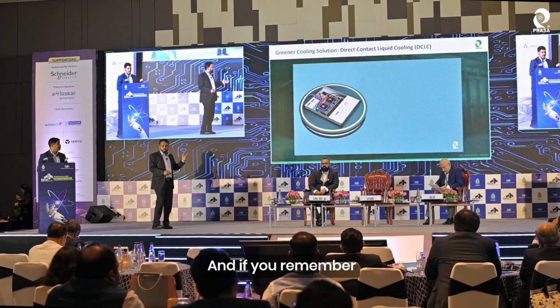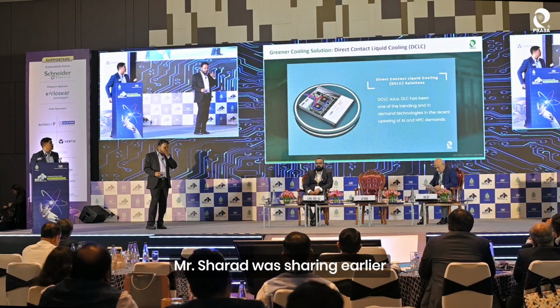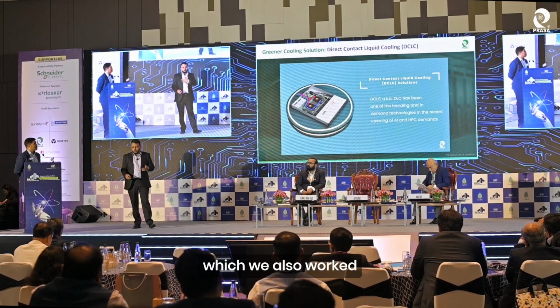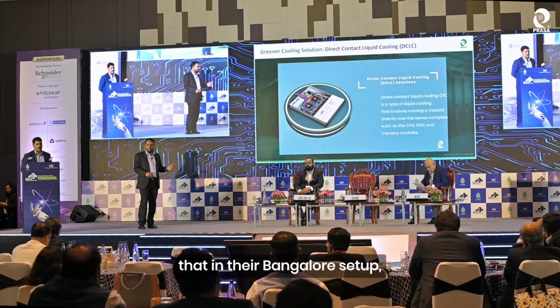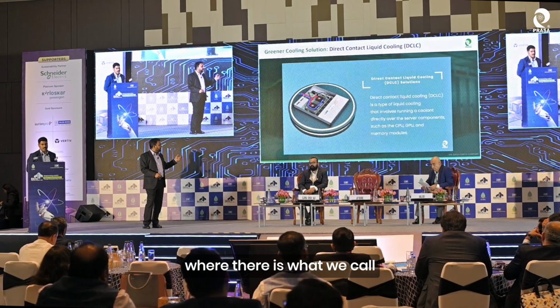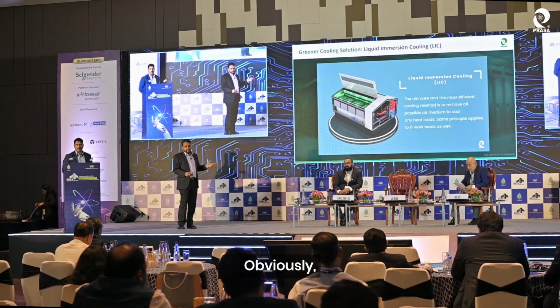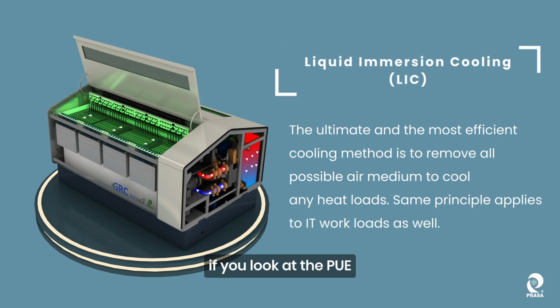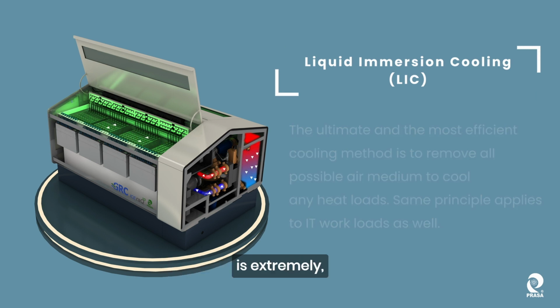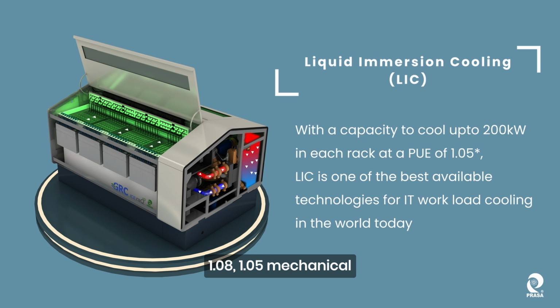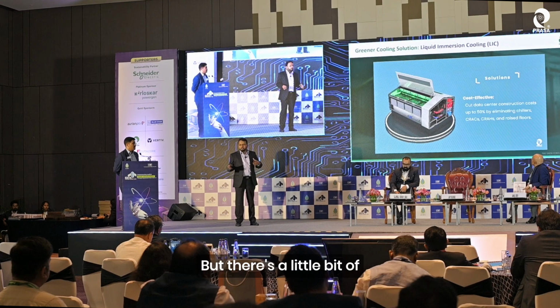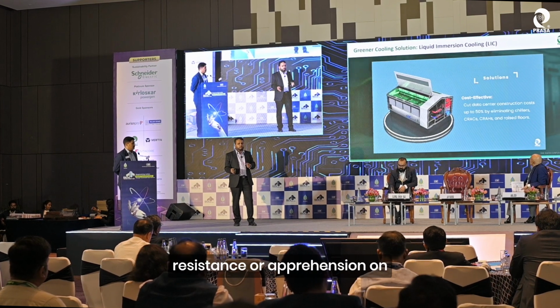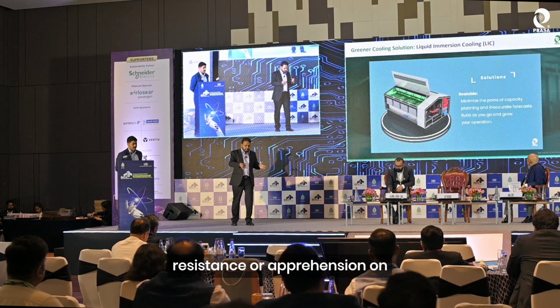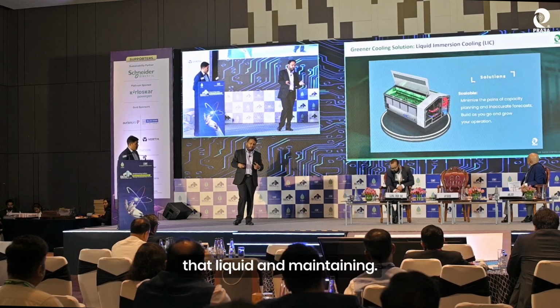And if you remember, earlier it was shared that there was a case we also worked on in a setup where we implemented what we call immersion cooling. If you look at the PUE comparison, which I'll show on another slide, you'll see that immersion is extremely efficient—1.08, 1.05, with a mechanical PUE of 1.03 as well. But there's a bit of resistance or apprehension about dipping servers into that liquid and maintaining it.